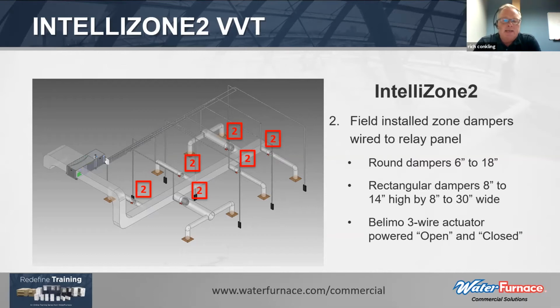actuator is to eliminate the need for the spring return, which typically is a common point of failure when you have actuators that are actuated for long periods of time and present that resistance against that spring. It becomes one of the weak links. It also allows us to have low amp draw for the actuators and allows us to put multiple zone dampers onto a single zone, or we could use just a single damper for a single zone. So again, different flexibility there for different applications of duct design.